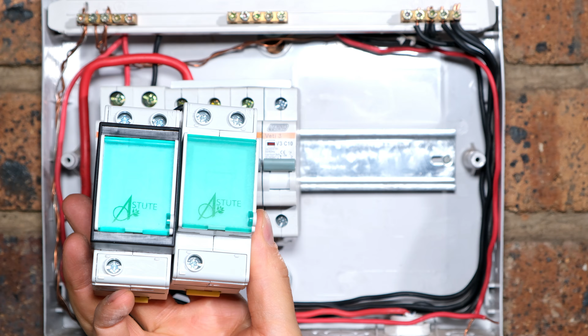In fact, you don't need to do anything here, so just steer clear of this part of the distribution board. Now, in order to install one of these timers, we will need a circuit breaker that feeds the timer. You'll need to choose a circuit breaker suitable for your load. For example, I'm going to use this 10 amp circuit breaker. This is sufficient for a small pool pump, and also sufficient for lights. Of course, you can use a slightly bigger circuit breaker, but this depends on what it is you are feeding.